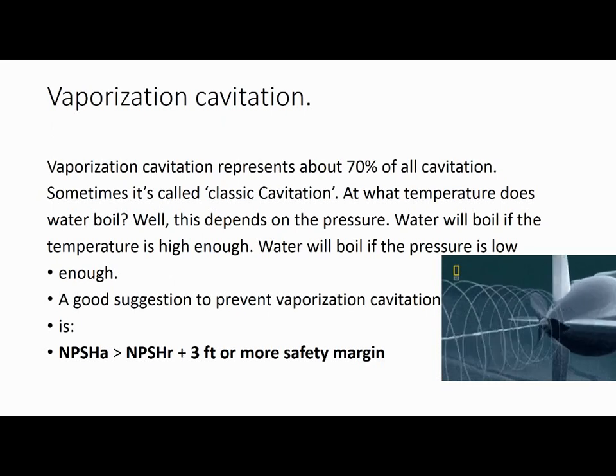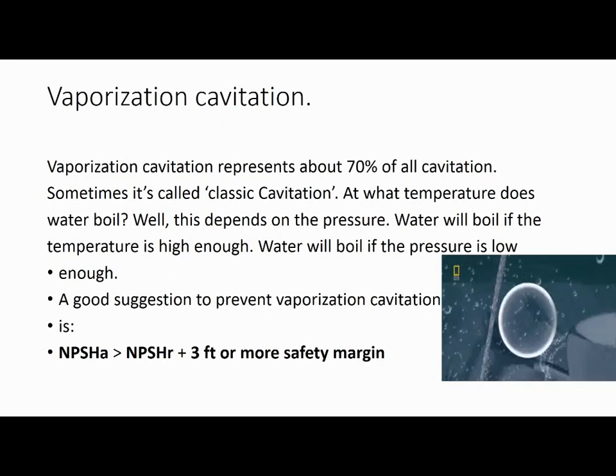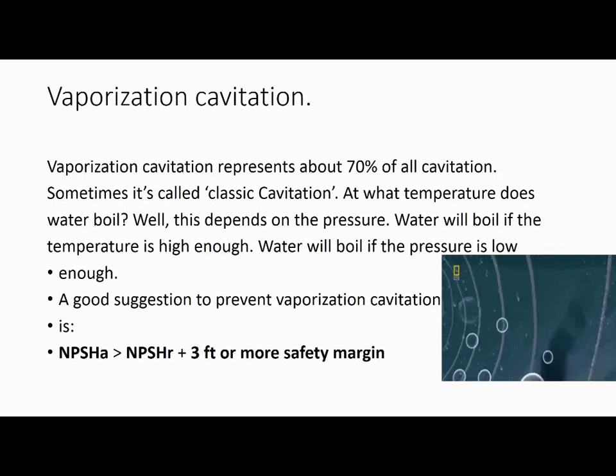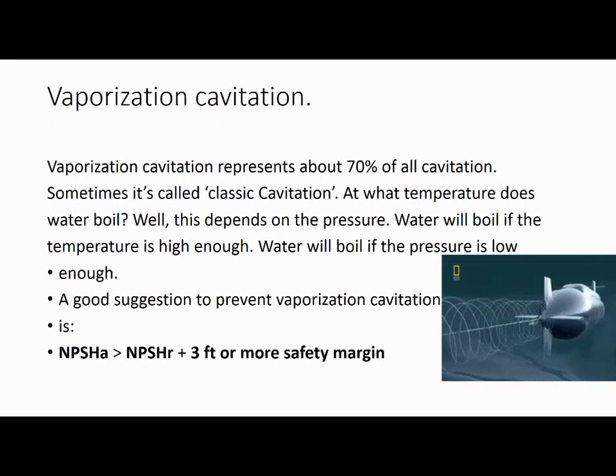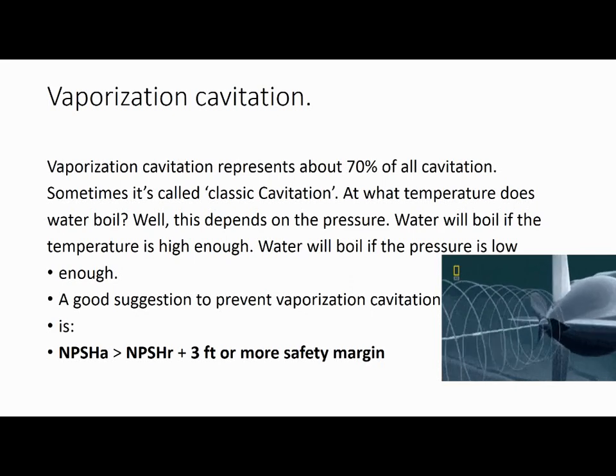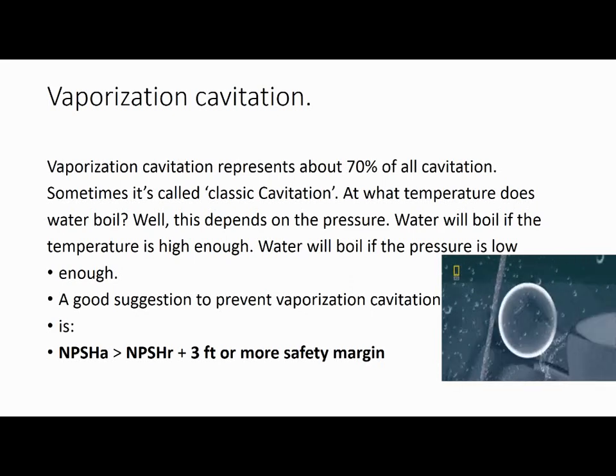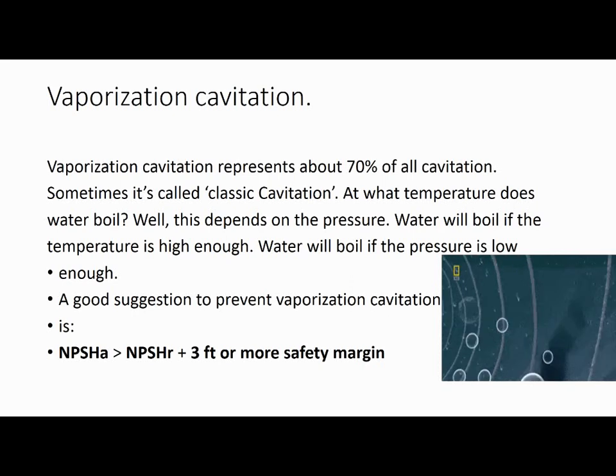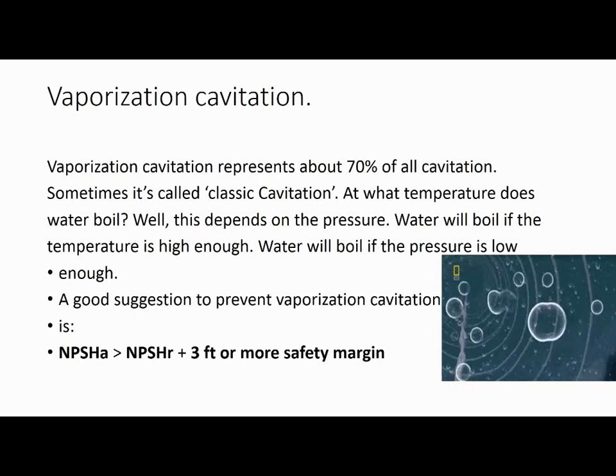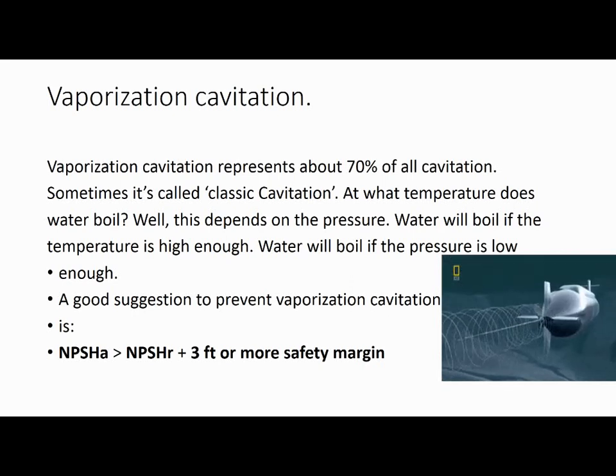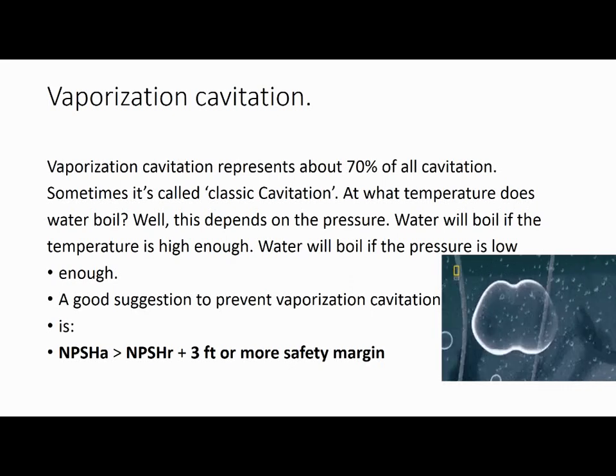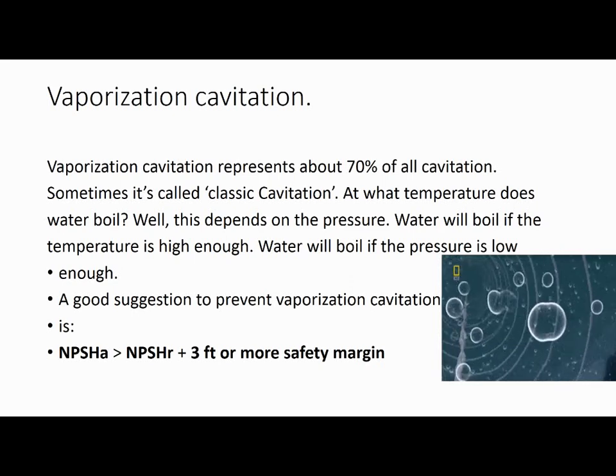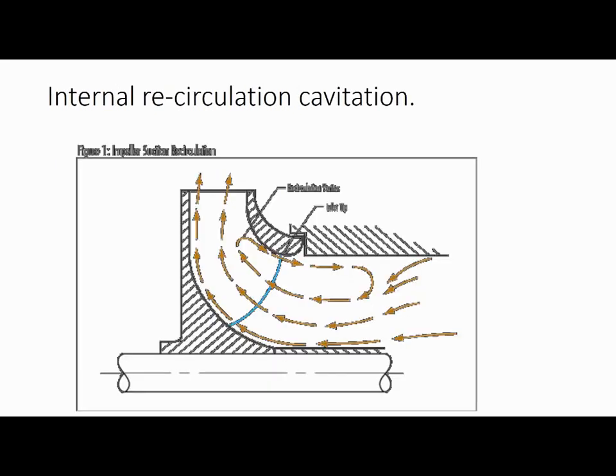Vaporization cavitation represents about 70% of all cavitation. Sometimes it's called classic cavitation. At what temperature does water boil? Well, this depends on the pressure. Water will boil if the temperature is high enough, and water will also boil if the pressure is low enough. A good suggestion to prevent vaporization cavitation is: NPSHA is greater than NPSHR plus 3 ft or more safety margin.